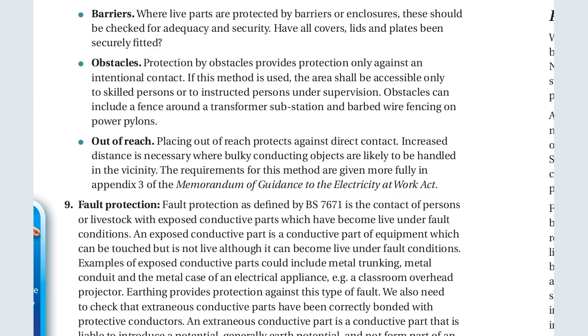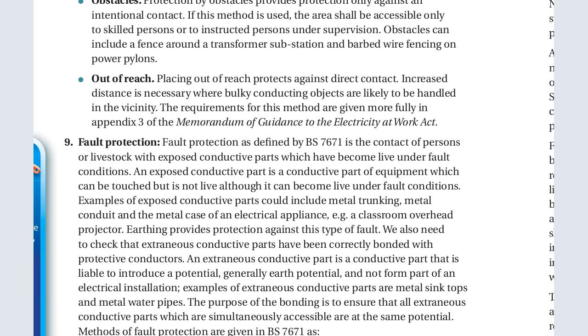So the requirements for these methods are given more fully in the appendix for the BS standard that we talked about. Another one is fault protection. How do we do the fault protection? So fault protection is defined by BS standard 7671 as the contact of persons or livestock with the exposed conductive parts which have become live under fault condition.